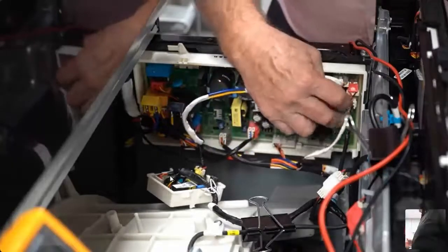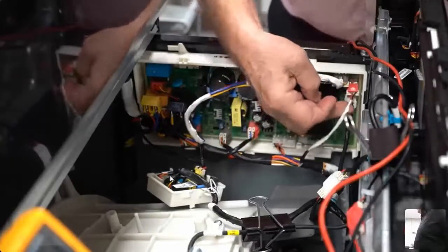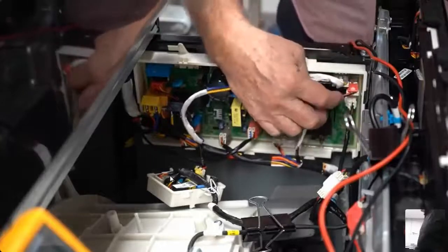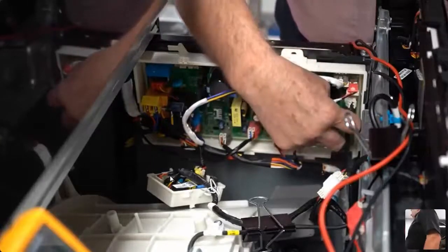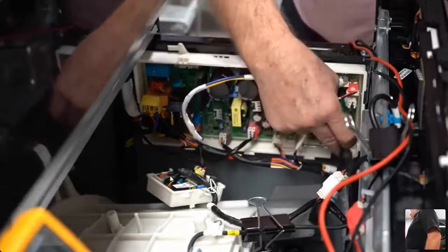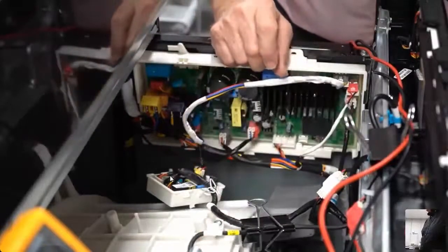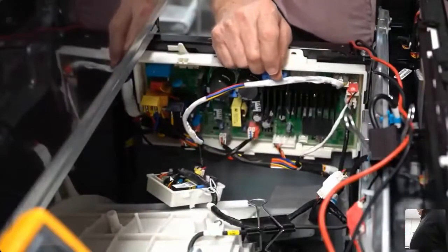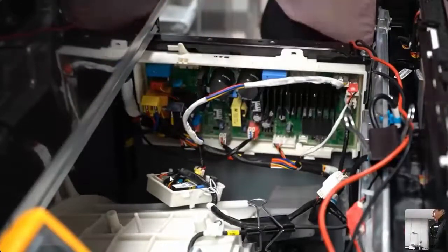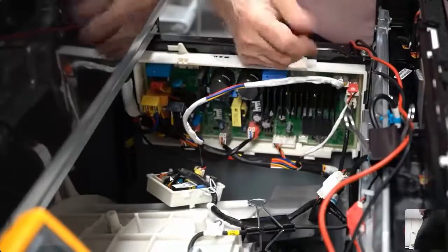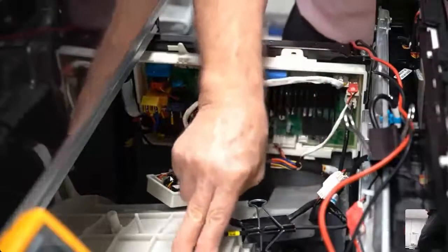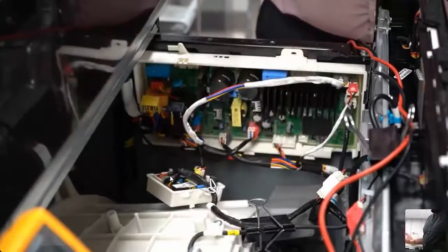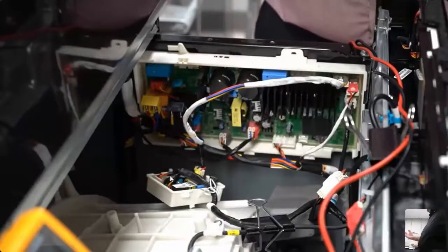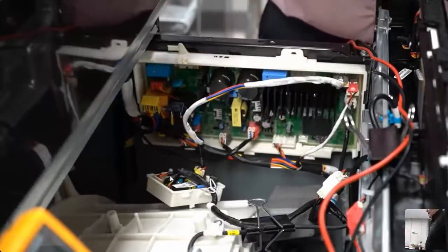Up in the top corner, I have your LED lights, and also a connection where you can test your vibration sensor. I'll get into how to check the vibration sensor a bit later - it's really simple. Also, your connections for your stator are located up in that corner. In most cases you don't want to do a voltage check there, you'd more likely do a resistance check.